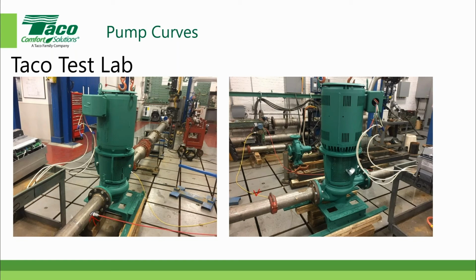So in laboratory conditions, we have very precise control conditions for the inlet and outlet conditions, and so the pressure at the pipe is the same as the pressure at the flange. Unfortunately, in the field, we don't necessarily get these nice 10 to 15 pipe diameters at the inlet and 5 to 10 pipe diameters at the outlet. And so we have to measure the pressure in the field at the pump flange itself. That's the most accurate place to measure it in the field, but in the laboratory, we measure it at the pipe. Hopefully that answered that question. Good answer.